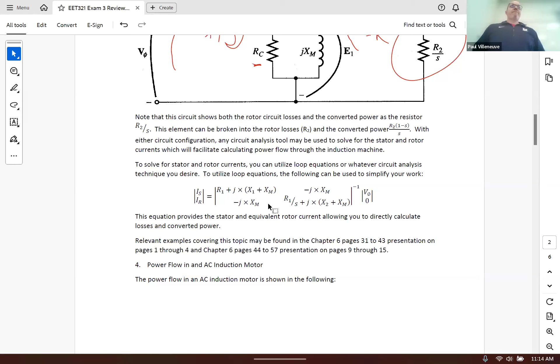All right, power flow. The nice thing about power flow is this is how you calculate losses and efficiency in an induction motor. Since we're only talking about induction motors, input power is always electrical, and this is a three-phase machine. We only did induction motors that were three-phase, never single-phase or smaller machines, because it doesn't make a lot of sense—they don't really exist all that often. Or if they do, you're not going to analyze them. You're going to buy a refrigerator and throw it away. You're not going to sit there and calculate what the load current is. You're just going to say, hey, this plugs into a 15 amp receptacle, it's good to go.